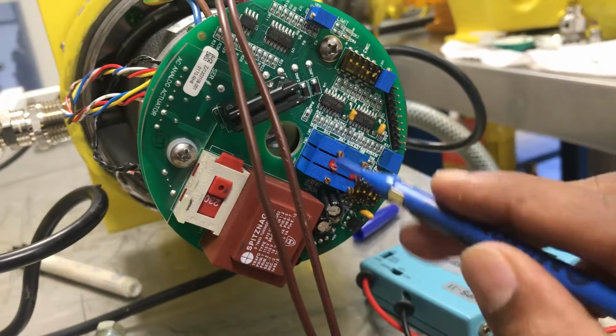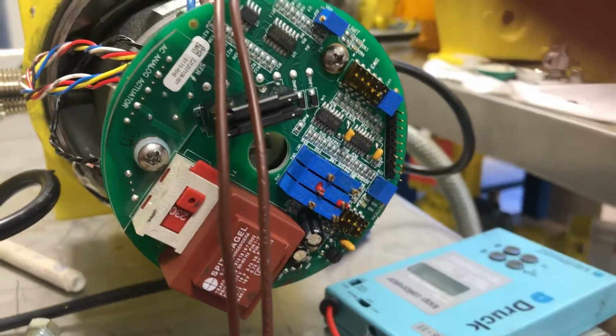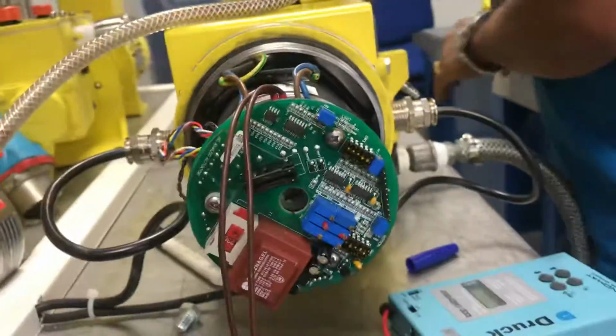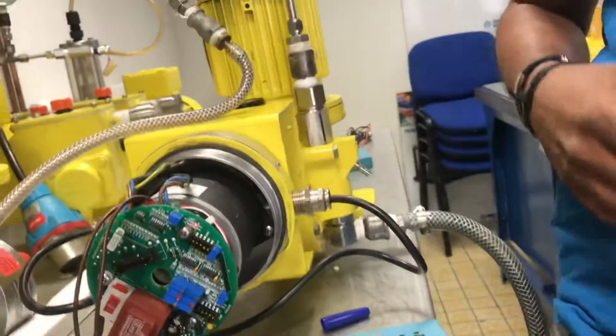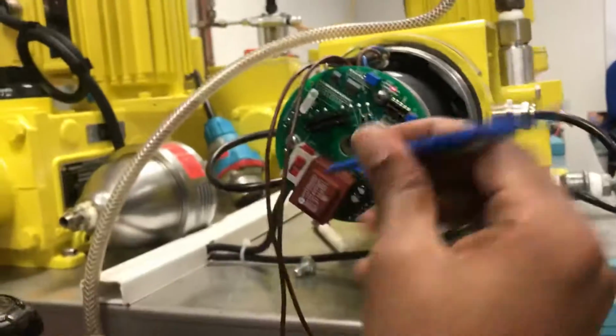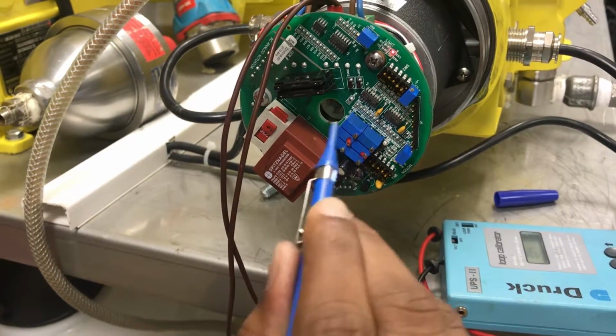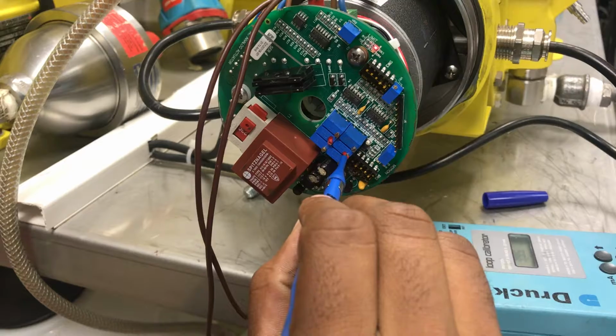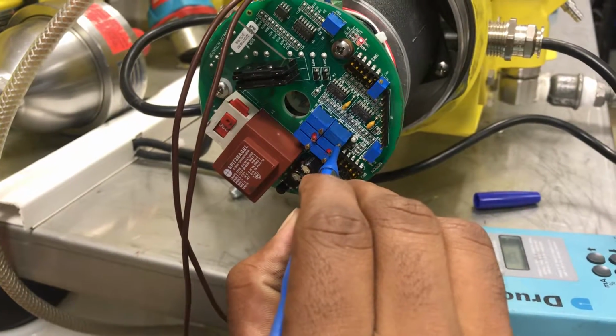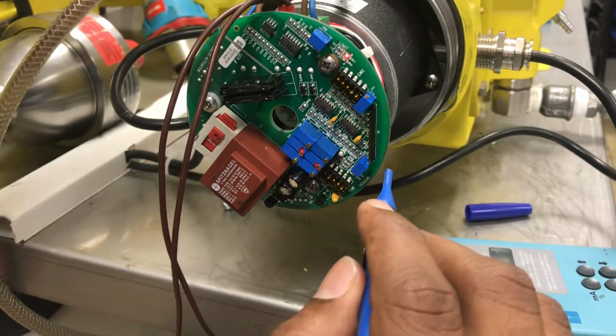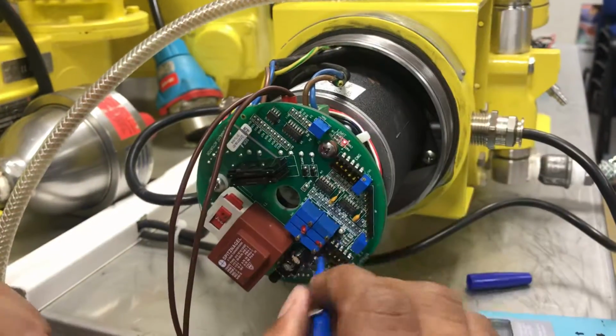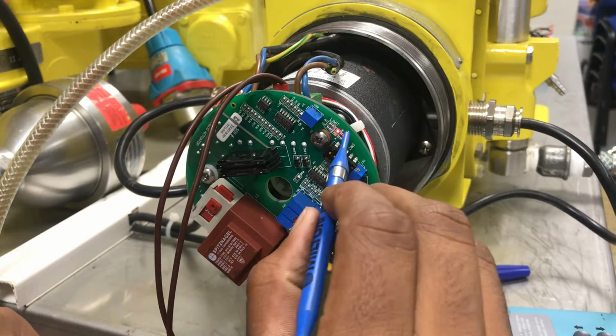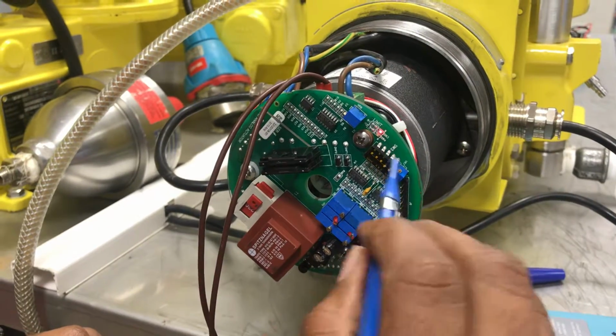This is the lower limit adjustment, this is the upper limit adjustment. Now physically we made the pump into 0, and now we need to make the actuator into 0. Now give 4 milliamp signal, and now this is the screw. If you turn this, the light will turn off, and you have to adjust this screw until the pump coupling and the actuator coupling match. Once it matches, you have to turn this again to make the light on. It will turn yellow, so it means you set it as 0.